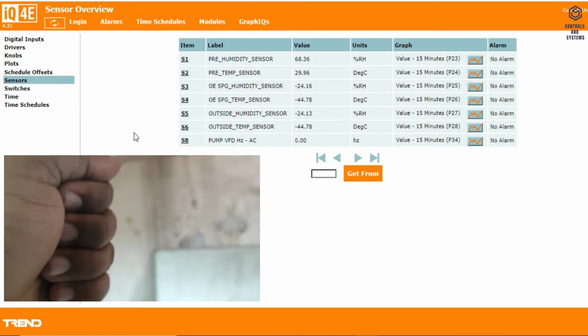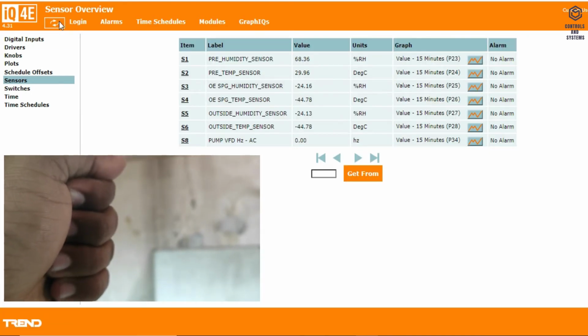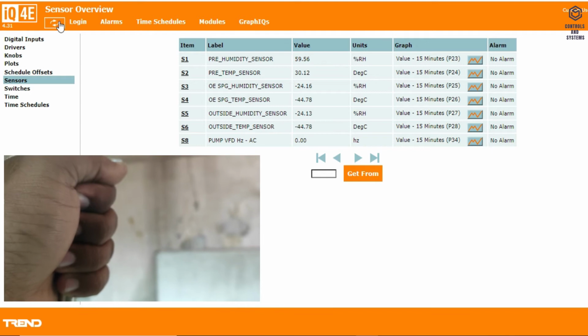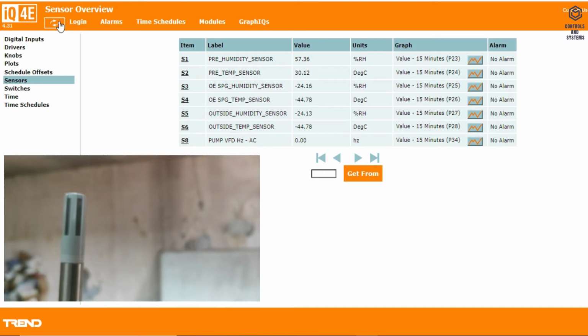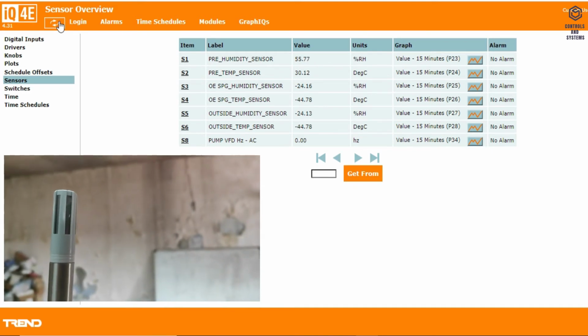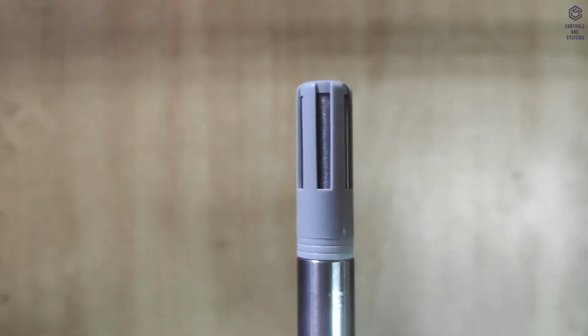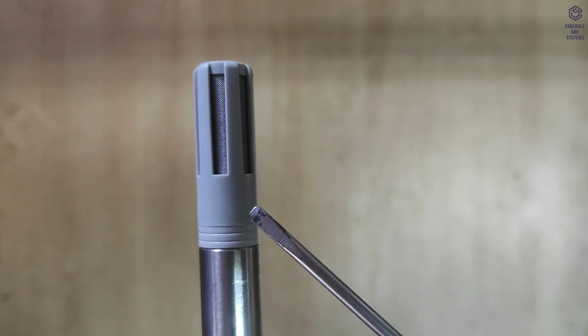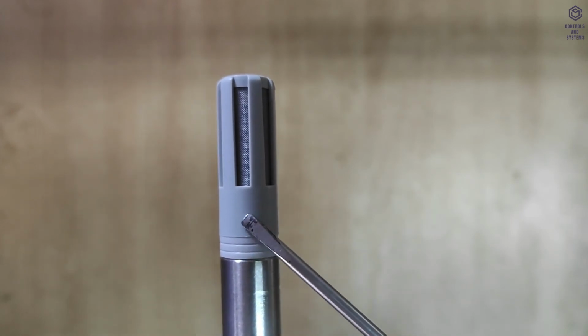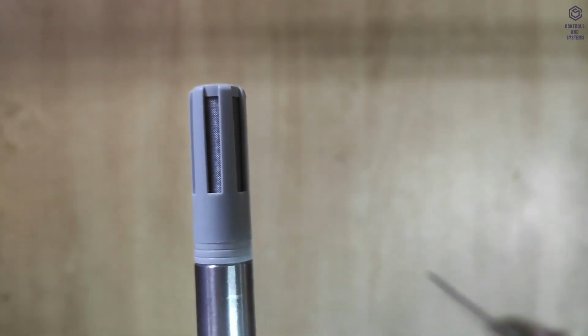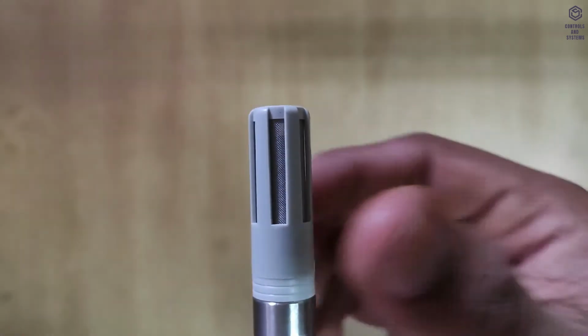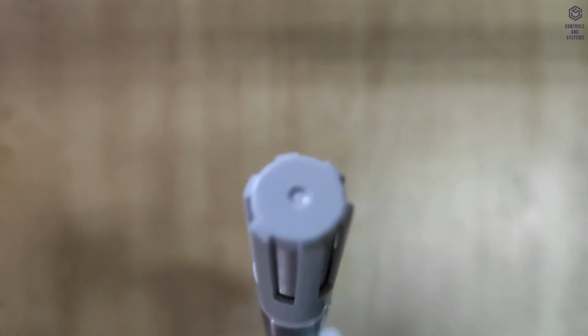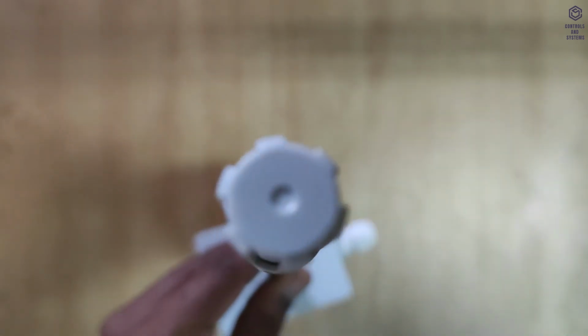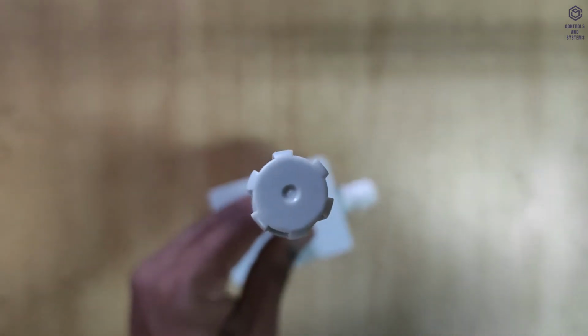I hold the sensor knob, and the RH and temperature values will increase gradually. Then I release my hand and the sensor value will come back to normal depending on the environmental condition. The product is equipped with a stainless steel filter. Since the sensor is an ESD sensitive device, you should avoid touching the sensor cap during operation. For maintenance purposes, it is recommended that you observe the valid ESD safety precautions. Please don't use it in a corrosive environment.